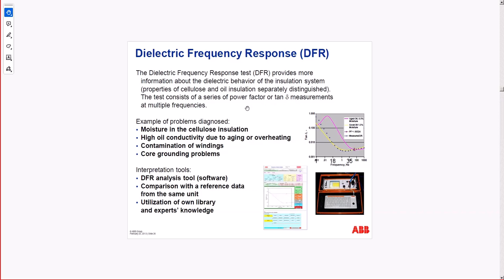Now, if we have moisture, at operating temperature, in the range of 80 degrees Celsius and above, we don't have much moisture in the paper. With the oil being hot, the moisture is in the oil, not in the paper, because the windings are hot. Once we cool down the transformer, that moisture will migrate from the oil into the paper insulation. That's why when we take oil samples, it's very important to mention when it was taken. You can take oil from the transformer at full power, or after it was cooled down. We need to know that, because the margins and results are different.